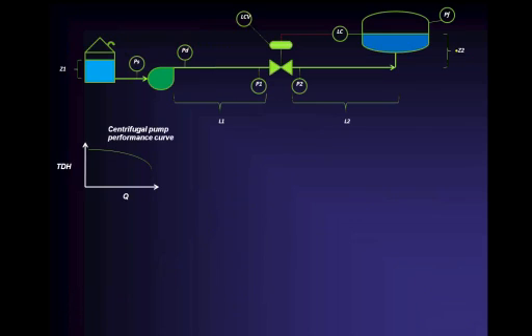All right, we've talked about the differential pressure across the control valve. I should tell you that I've had personal experience, and therefore I have to take time out for this lecture. Forgive me if this is under your head, many of you. But I've had customers call me and say, "Hey, Mike, I need a valve. It's got to deliver 100 gallons per minute of water. I've got a 2-inch pipe, but it's got to deliver 100 gallons per minute of water over to my demineralizer and 60-degree water." And I say, "Oh, that's great. Can you tell me what's the valve inlet pressure and the valve outlet pressure while I'm delivering that 100 gallons per minute through the valve? I need that to do the sizing of the valve."